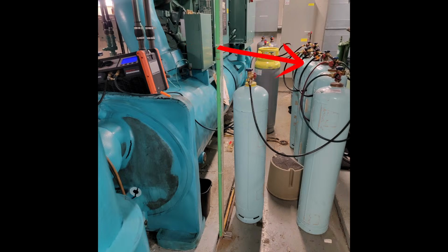So basically what I've done is speed up the process. Instead of hooking and unhooking every single tank one at a time, we ran them all in series together. This is specifically for charging. I'm pushing out of the recovery unit into the vapor side of this tank, out of its liquid line into the vapor of the next tank, and so on, all the way through, until the final tank's liquid line feeds into the chiller.